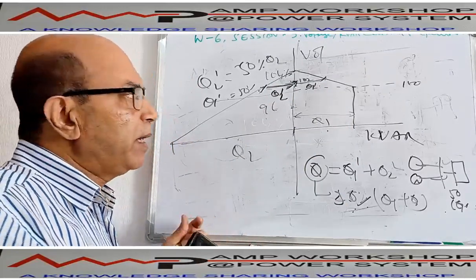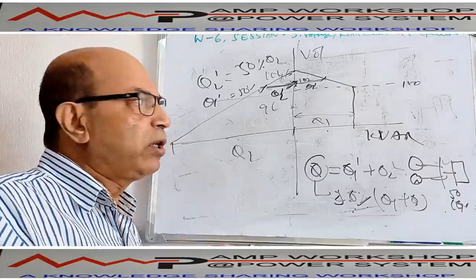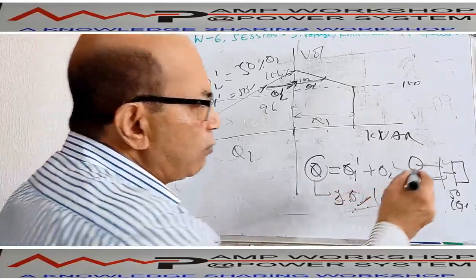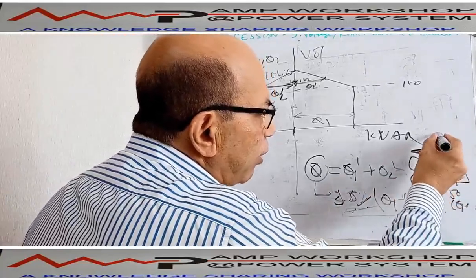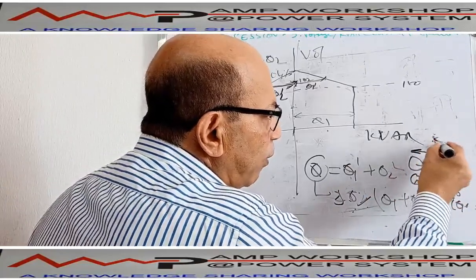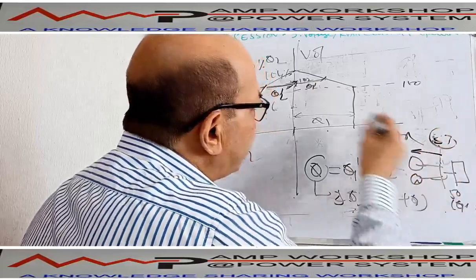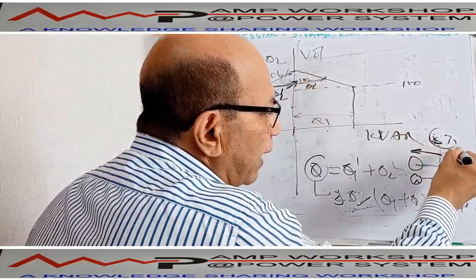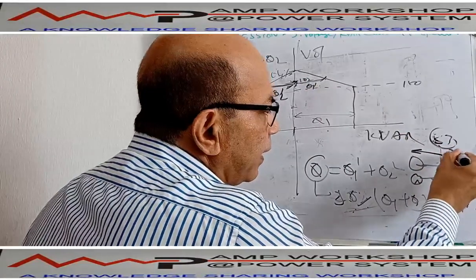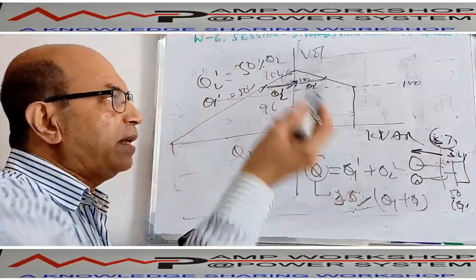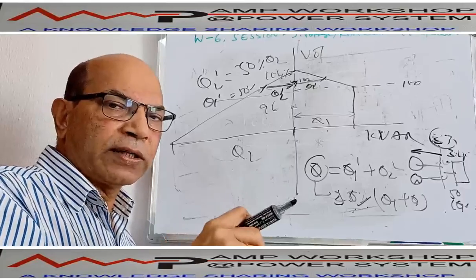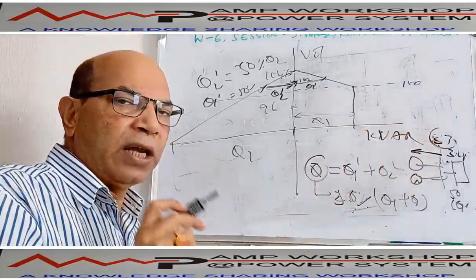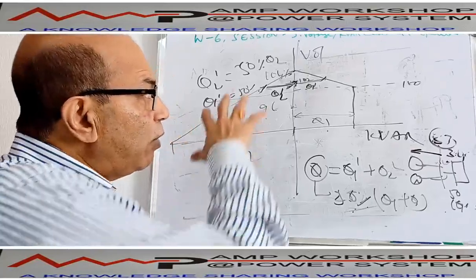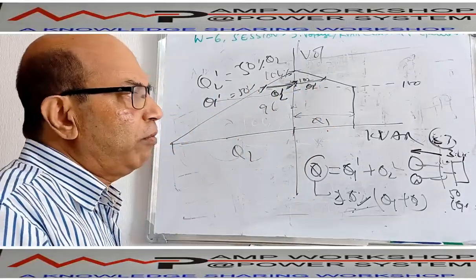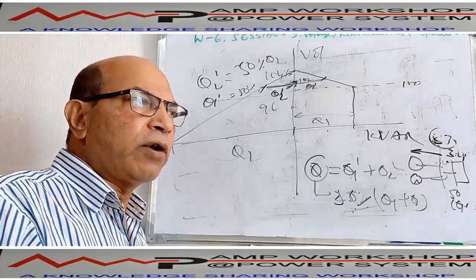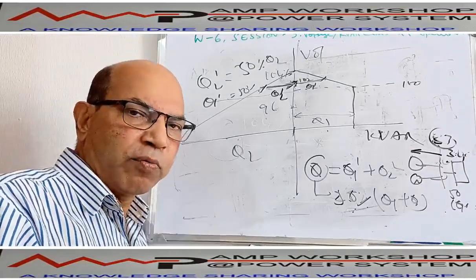unstable, but here it will not run with a constant voltage. When this 50% load is there, if you measure the bus voltage, suppose it is 3.3 kV, a 2% drop will be there. So it will be running at about 3.23 kV. It will be running at this voltage. If you want to bring back the rated voltage, you have to manually control the excitation and bring it to 3.3 kV and keep it for operation. This is called the droop voltage control mode of operation. So these are the two modes of operation: one is isochronous voltage mode, another is droop voltage mode.